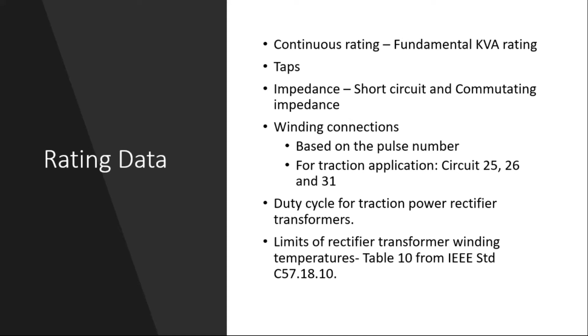Next, we have winding connections. We have many different winding connections covered in the standard. Some of them are circuit 25, 26, and 31. So, for example, circuit 25 has both HV and LV as delta and delta. And this is like a 6 pulse, it has only 2 windings. When it comes to circuit 31, we have 2 low voltage windings.